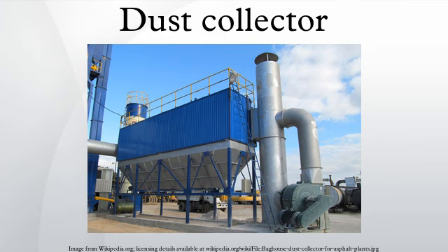Characteristics of dust. Moderate to heavy concentrations of many dusts can be abrasive to dry centrifugal collectors. Hygroscopic material can blind bag collectors. Sticky material can adhere to collector elements and plug passages. Some particle sizes and shapes may rule out certain types of fabric collectors. The combustible nature of many fine materials rules out the use of electrostatic precipitators.